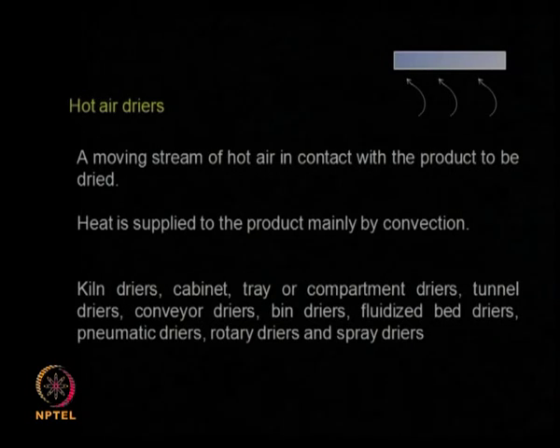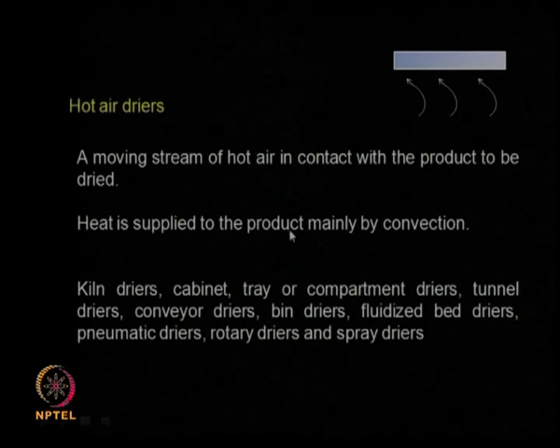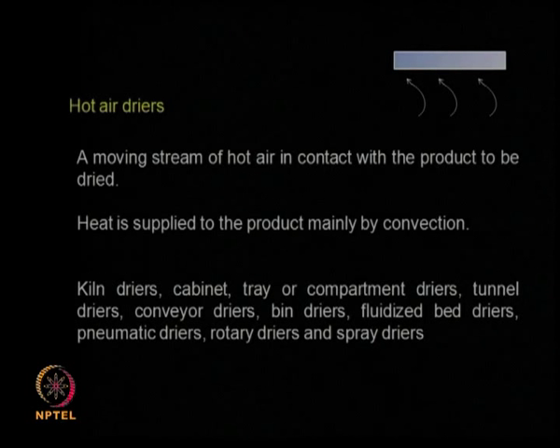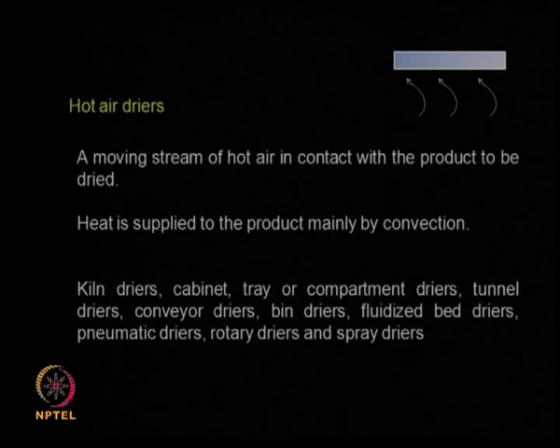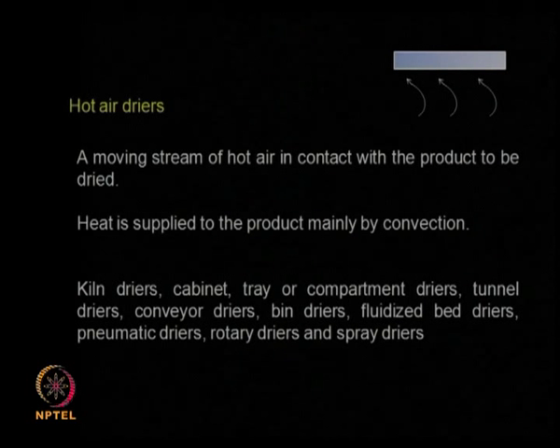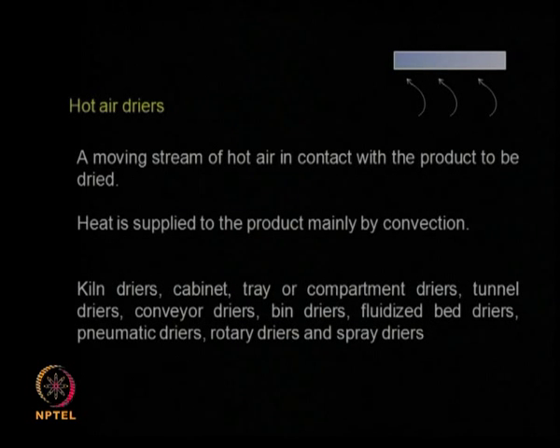Hot air dryers work because hot air flows past the material — heat transfer is through convection only. There are many types: kiln dryers, cabinet dryers, tray or compartment dryers, tunnel dryers, conveyor dryers, bin dryers, fluidized bed dryers, pneumatic dryers, rotary dryers, spray dryers — all based on hot air coming in contact with the solid, which carries the moisture away. There is no direct contact between the solid and the heating element. Convection means factors like flow rate, turbulence, and temperature difference all govern the rate of heat removal.